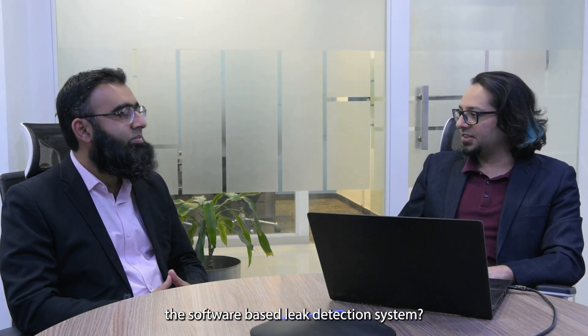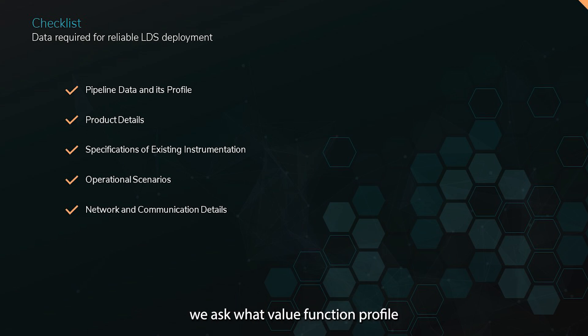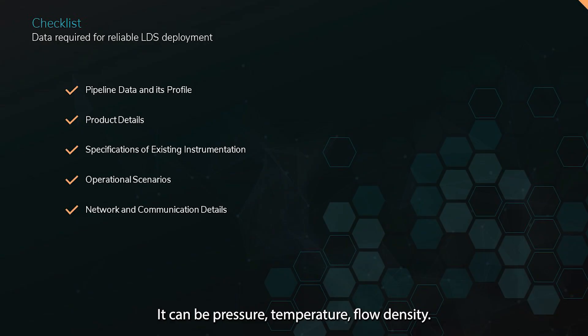What is the minimum infrastructure needed to implement a software-based leak detection system? We ask pipeline operators to share pipeline information including pipeline characteristics — as mentioned, we need that information to build the digital twin — as well as product details, elevation profile, and the existing communication infrastructure. We also assess the accuracy of existing instruments. If the current instruments provide the required level of accuracy, we can proceed with them; otherwise, we propose a new set of highly accurate instruments. These would typically include pressure, temperature, flow, and density instruments — standard process measurement instruments.